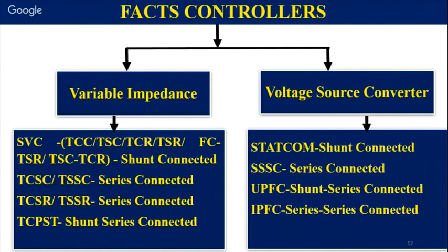If there had been FACTS, if sufficient reactive power compensators had been installed in the lines, they would have met the increased load, and there would not have been loss in the transmission line, and all this that we have discussed. So FACTS controllers are basically classified as variable impedance type, and the other is variable voltage source converter type.